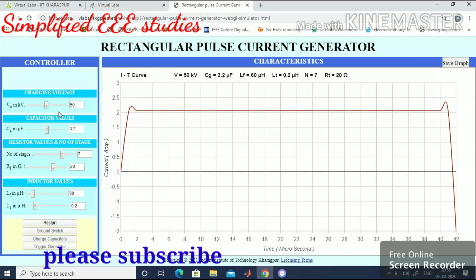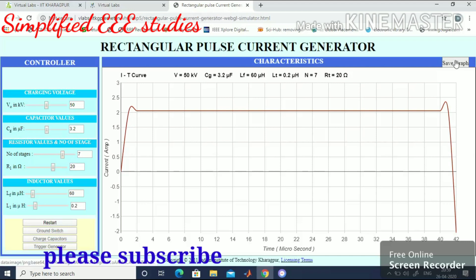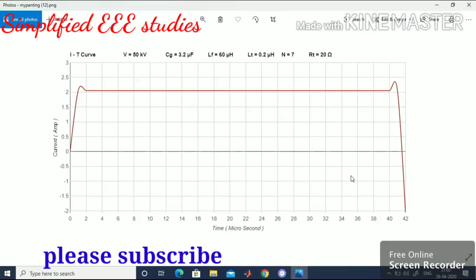These are the parameters set from the control panel. After setting all parameters — start, then ground switch, then charge capacitors, then trigger generator — you get the rectangular waveform. This wave shape is used for testing of lightning arresters and surge protection devices. By using LC elements, we can change the wave shape. You can save the graph or take a printout for your records. This is how to generate a rectangular current pulse using this type of rectangular pulse generator.